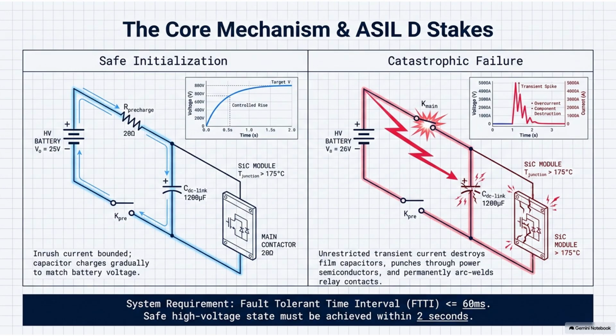Spot on. Mechanically, the pre-charge sequence routes the high-voltage electricity through a dedicated, highly resistive pathway, called the pre-charge resistor. So it acts like a bottleneck, artificially limiting the flow of current. It forces the DC link capacitors to charge up on a controlled, predictable curve over just a few hundred milliseconds.